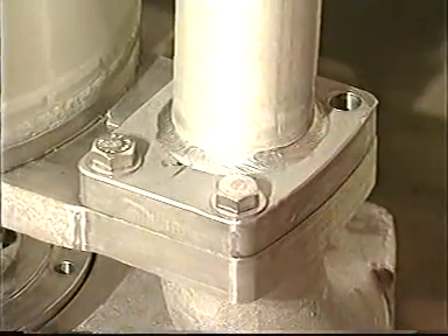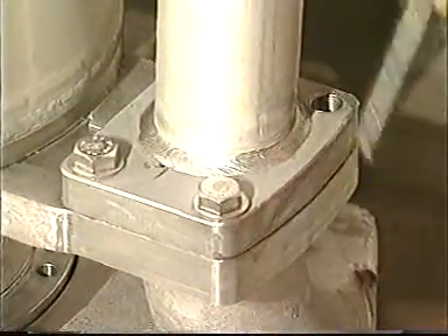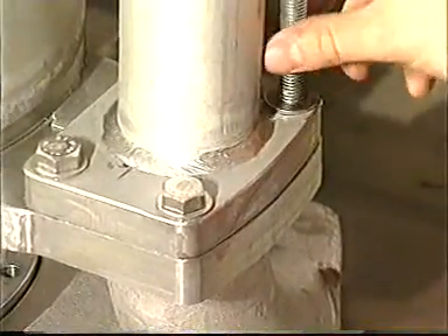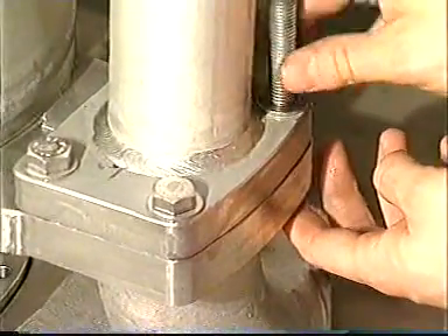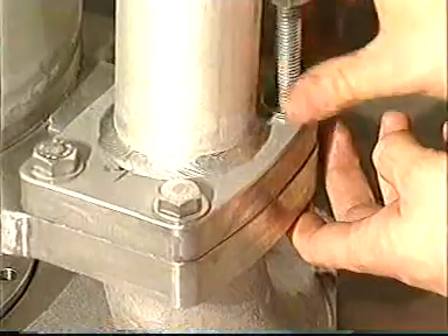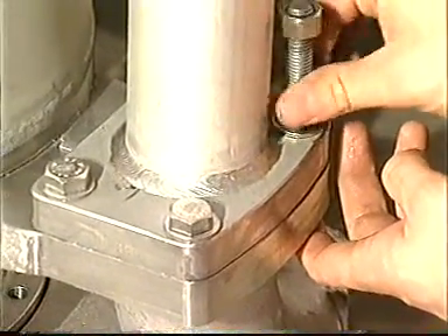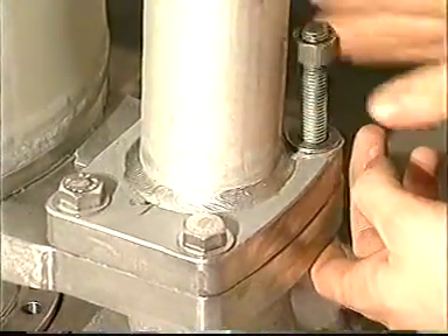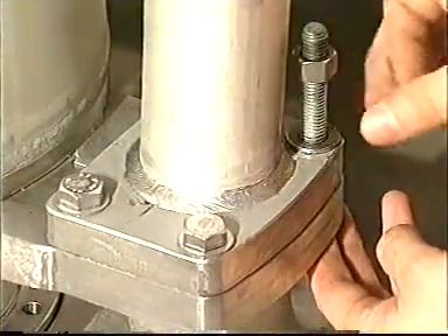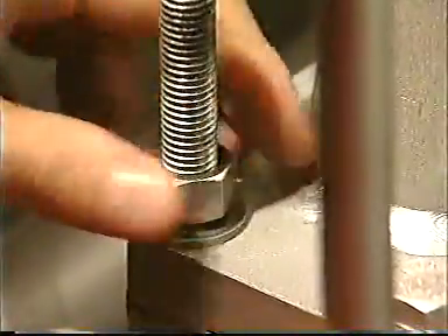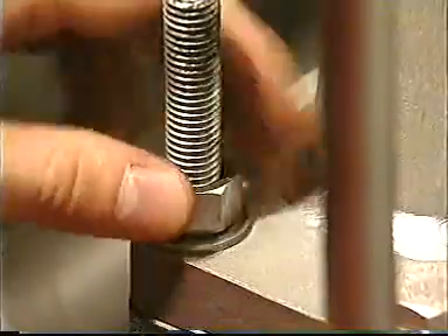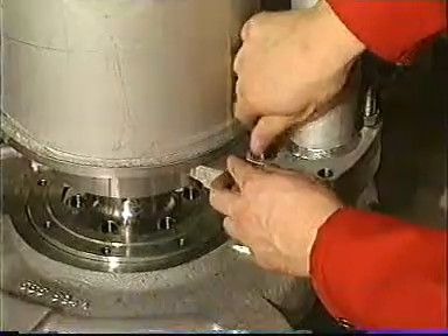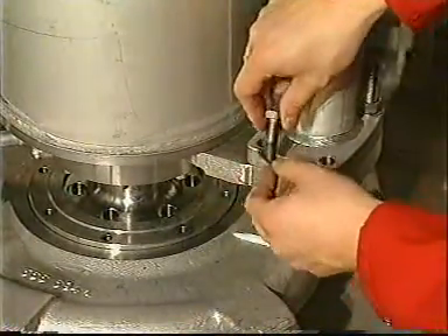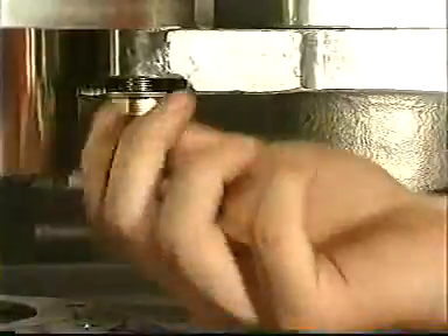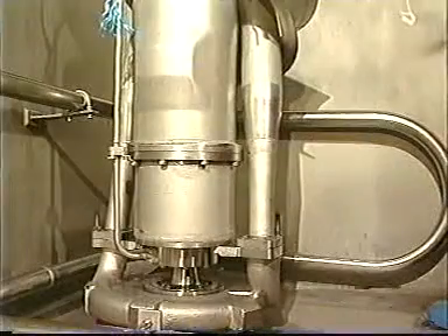Then remove bolts between volute casing and cargo leg. Change 2 of the bolts with lowering, lifting bolts. 1 bolt in each leg. Remove rest of the bolts on cargo flange and also between volute casing and bearing housing.